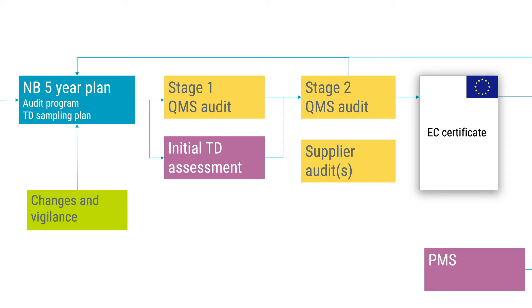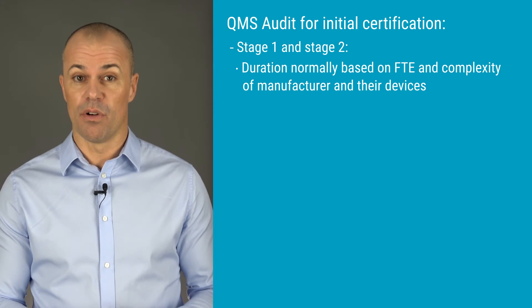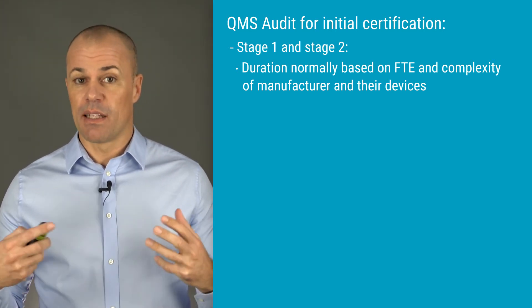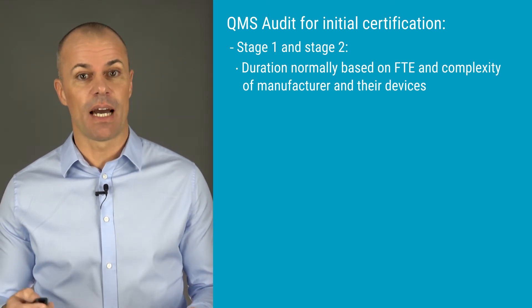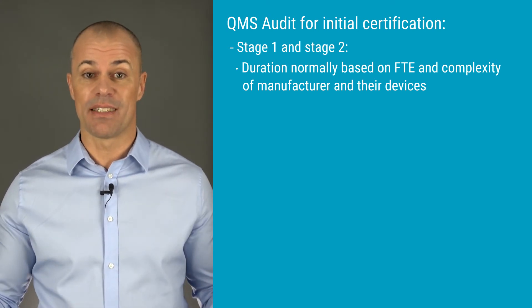My best tip to all manufacturers is to send in only complete and well-structured technical documentation to avoid delays. When the stage two audit has been performed, any non-conformities have been properly addressed, and the initial TD assessment is reported with any potential non-conformities addressed, then the first MDR EC certificate can be granted by the notified body. The extent of initial and coming audit activities normally depends on the size of the manufacturer and the extent of their QMS. For a manufacturer with approximately 10 employees, the initial audit will take somewhere around 5 days in total, and for a manufacturer with 100 employees, approximately double.